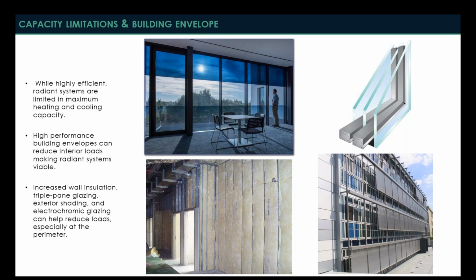So looking at triple glazing, looking at increased insulation at the exterior, looking at both external shading and internal shading, whether that be motorized shading or electrochromic glazing. All of these things can help reduce the envelope load in the building and get the BTU per square foot requirement in the space down such that you can then apply these radiant systems. So the envelope is very, very important in making these systems happen.